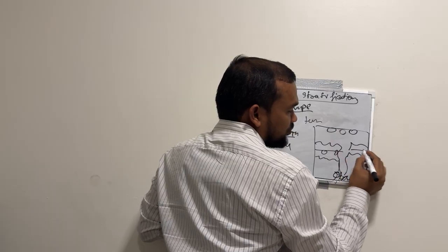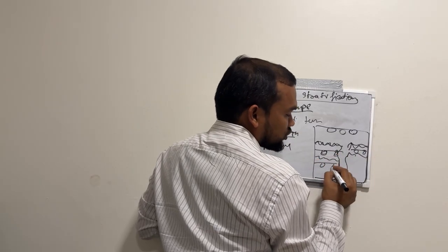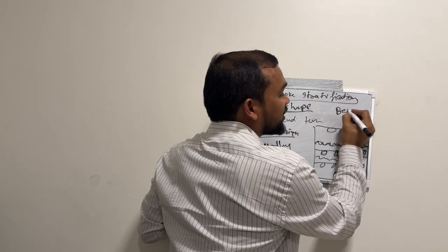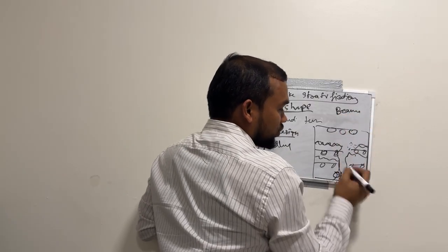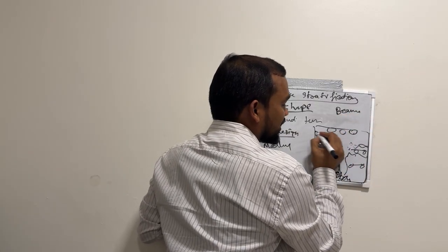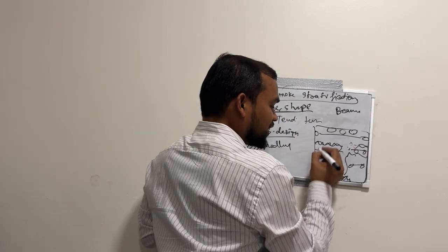So in this case, we will add multiple layers before and after the stratification layers. We have to install multiple layers of smoke detectors. We have to check beam detectors, and we have to install them in many locations based on the height. Beam detector here, beam detector here.